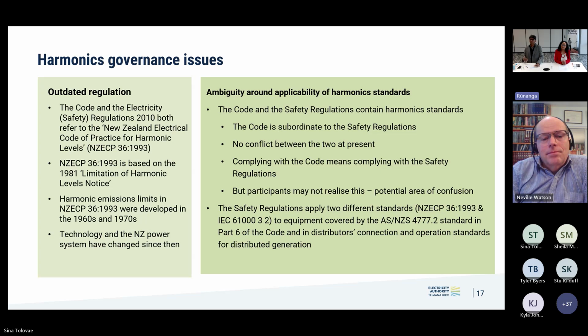But the issue comes in how the user interprets it. What we found from one-on-one engagements with industry stakeholders is that some utilities are using NZECP to allocate harmonic limits to generators as well, whereas NZECP clearly states it's only meant for loads. We do not have anything specific for generators.